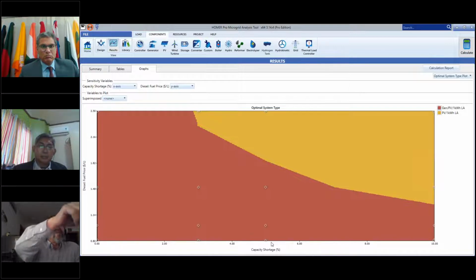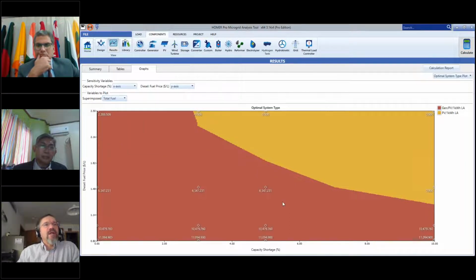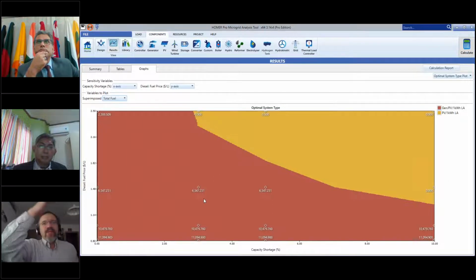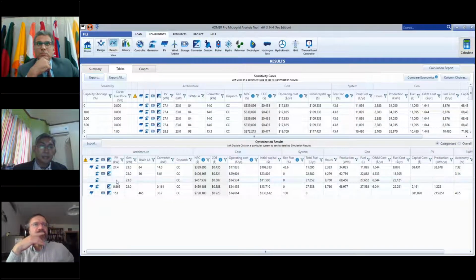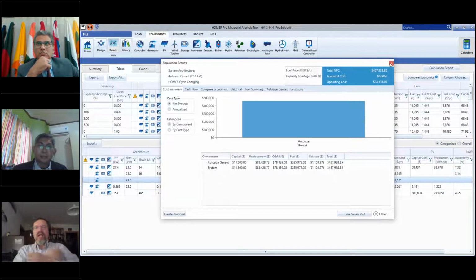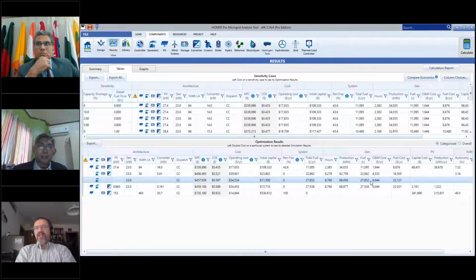If you put in the superimposed variable for total fuel consumption, you can see that even though you have a generator, it's only using a few thousand liters per year. If you go back to the table, the generator-only case was using about 27,000 liters—quite a lot more fuel. So even with inexpensive fuel at 80 cents a liter, and even wanting 100% reliability, the hybrid system is cutting your fuel consumption significantly, maybe 40-60%, I'm just estimating.